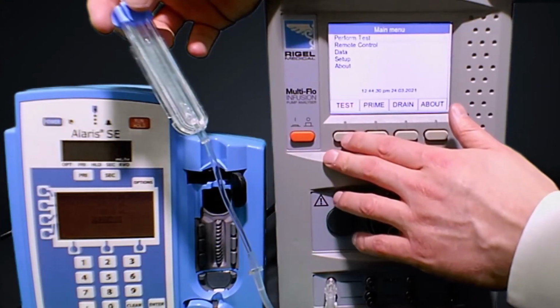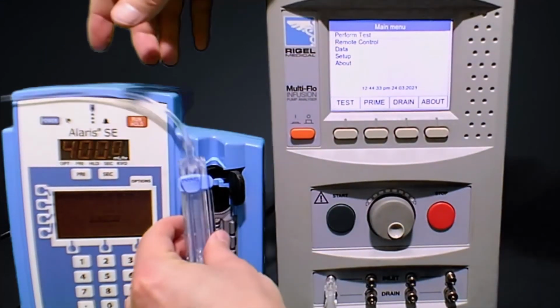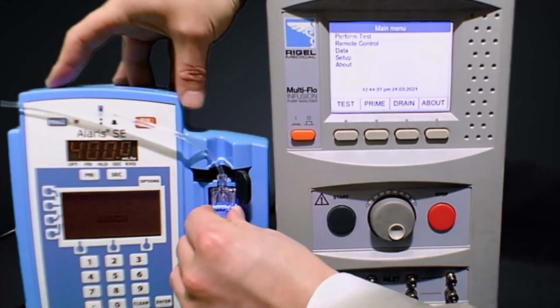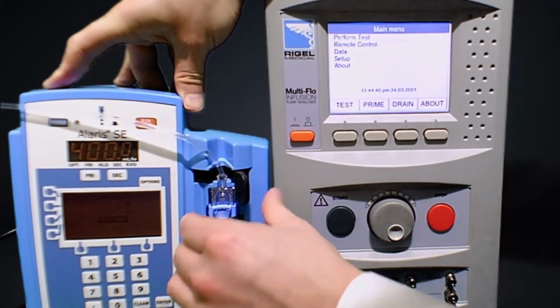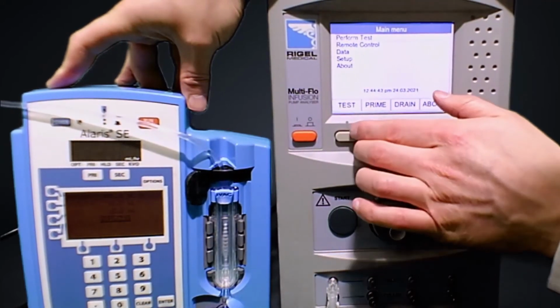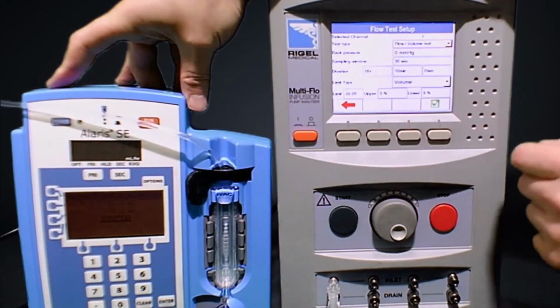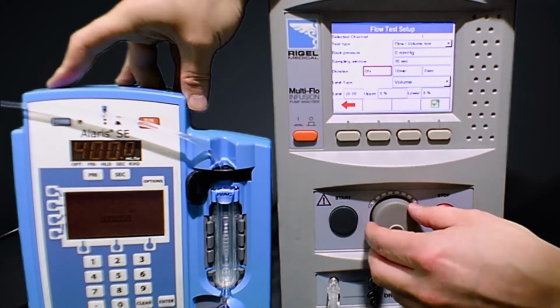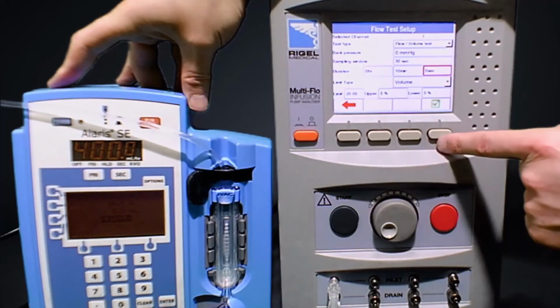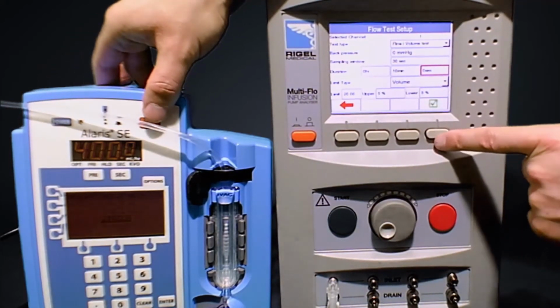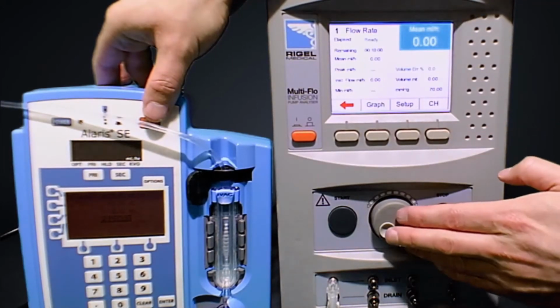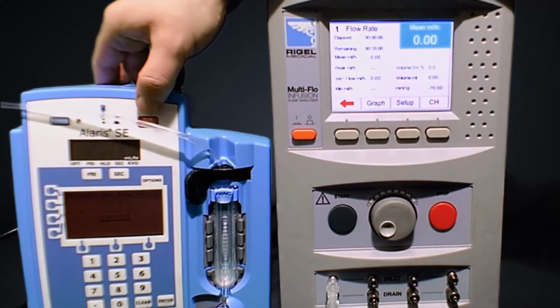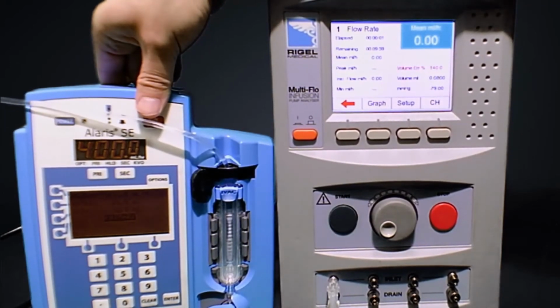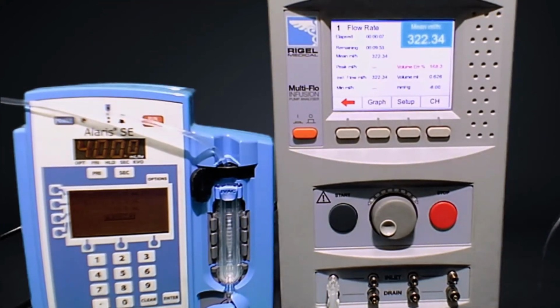We're now ready for a manual test. We've shut off the IV giving set and plug it into the infusion device. Okay, so that's clicked in. We'll lock that in and then we'll run to test, and we're going to use manual test, which is F4. Now the parameters aren't too clear on here, but we're just going to leave the settings as they are. We've got volume to be infused 20 ml, but I'll show that on the screen a bit closer so it's more clear. We always push start first on the infusion device analyzer, and then we select run on the infusion device itself. The Multi-Flo will always wait for any volume to be infused before carrying out a measurement.